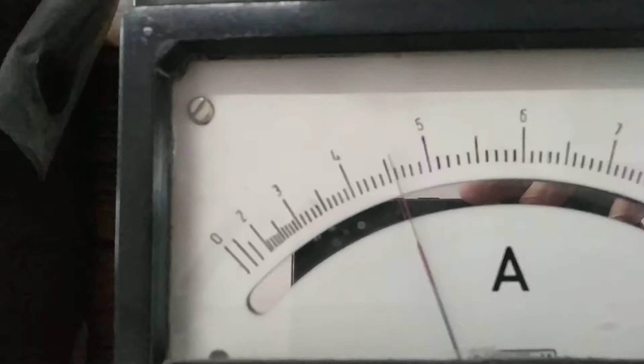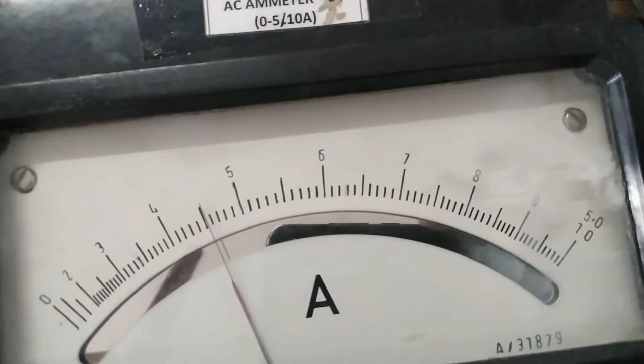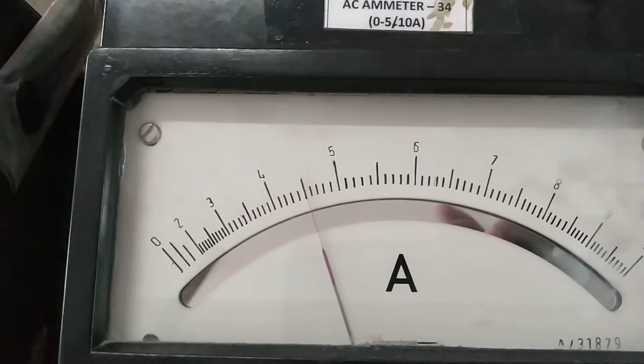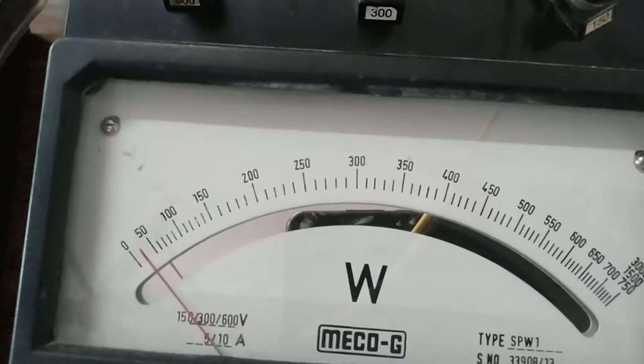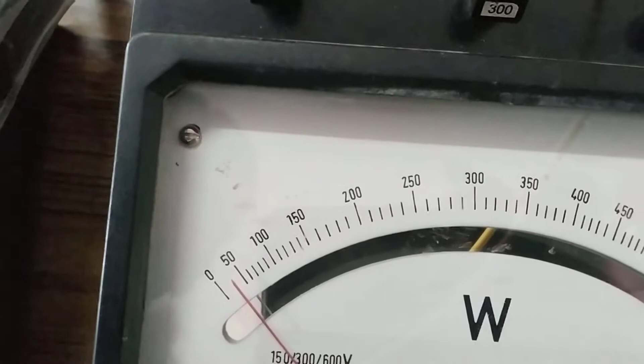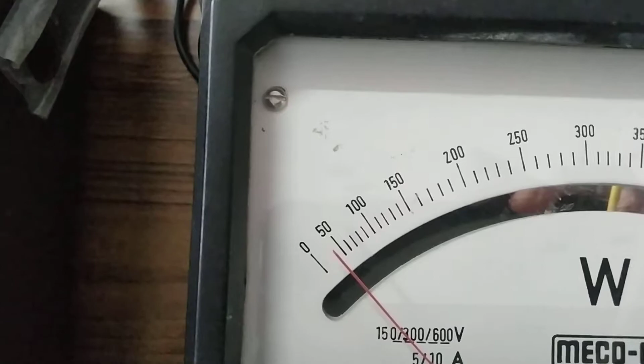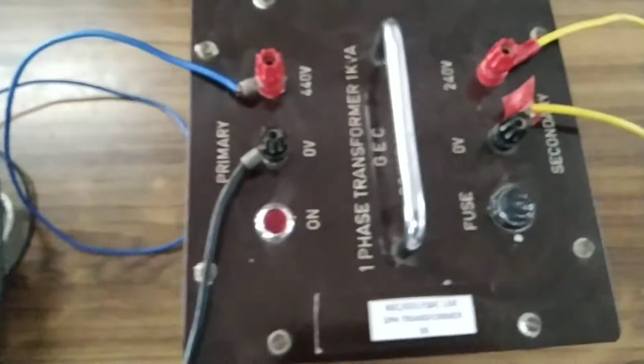On the ammeter we have 4.5, which is nothing but 2.25. Since the scale is in 10 ampere, for the 5 ampere terminal we need to divide by 2, so 4.5 by 2 is 2.25, which matches the 2.27 rated current. Now the wattmeter range is 0 to 50. If you go errorless, it will be near 40, not in the mid. We are getting near 40. So we note down all the values.